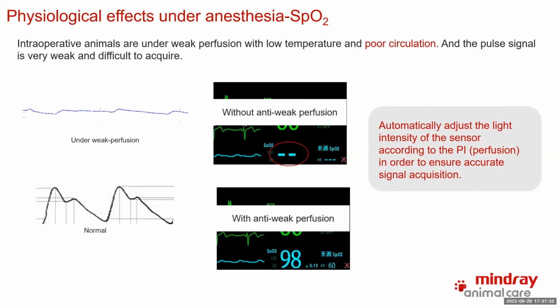And also for some weak patients during the surgery, maybe they have weak perfusion and low temperature, and the circulation is very poor. So their pulse signals will be very weak and difficult to acquire. If we're facing this kind of situation, our machine will detect the weak signal and then automatically adjust the light intensity of the SpO2 sensor. When we adjust the light intensity, it will also amplify the signals, and it can measure to get the SpO2 result according to the perfusion.